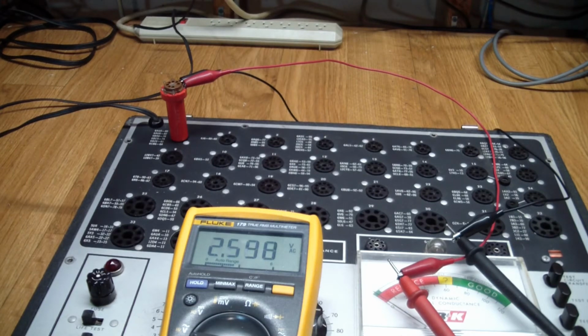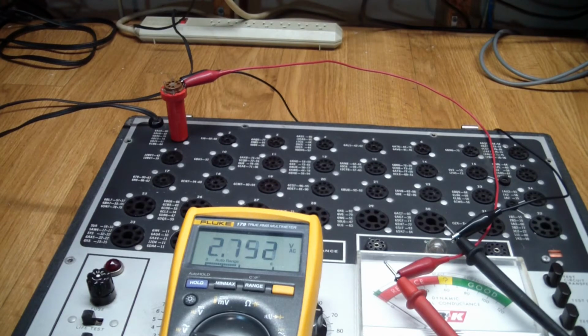Now, with no test button pressed, we're getting a voltage that is pretty high compared to what we're supposed to adjust it to. And what I figured out finally is it's the same problem I had with the Hickok tester, and that is this expects a VTVM and a 10 meg meter. A meter with 10 megs input impedance doesn't provide it with any load. This expects a load.